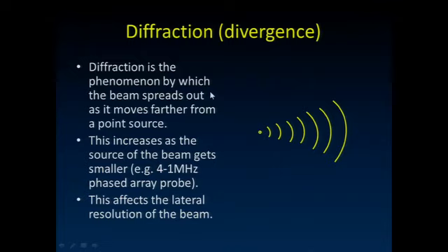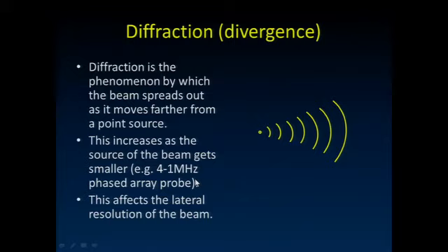Diffraction also occurs: although we want the ultrasound beam to travel as a thin pencil-like beam, it tends to diverge as it goes deeper. This divergence increases as the source gets smaller, as with phased array transducers. It doesn't affect axial resolution, but the ultrasound wave gets wider and more spread out with depth, reducing our lateral resolution.